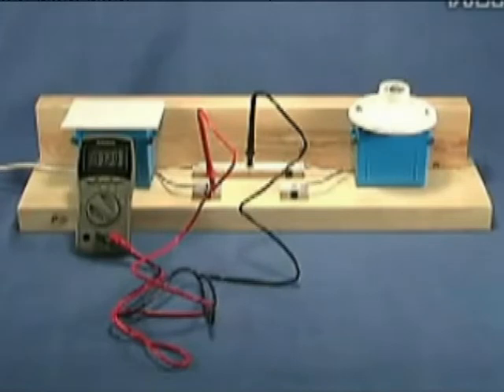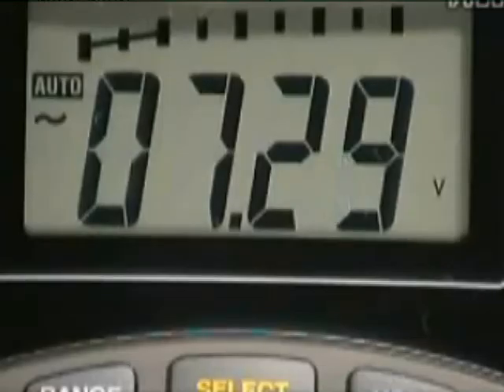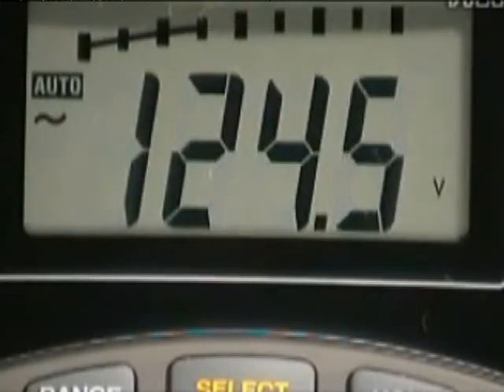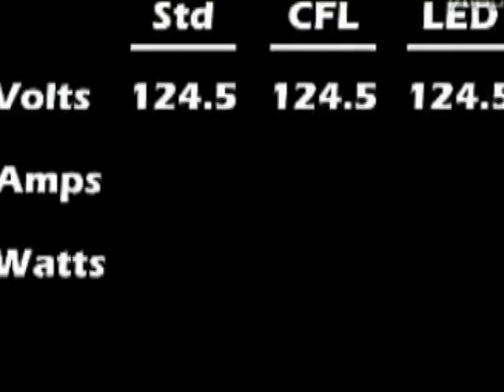You'll notice that even with the device turned off, we're measuring a small voltage. This is a phantom voltage, likely due to electromagnetic interference or coupling, which shouldn't be a problem. When the device is turned on, you'll see the voltage jump significantly. If we zoom in on the multimeter, you can see that when the testing device was turned on, the voltage jumped from about 7 volts to 124.5. This voltage should be consistent for all 3 light bulbs, so we'll go ahead and enter it in the data table.